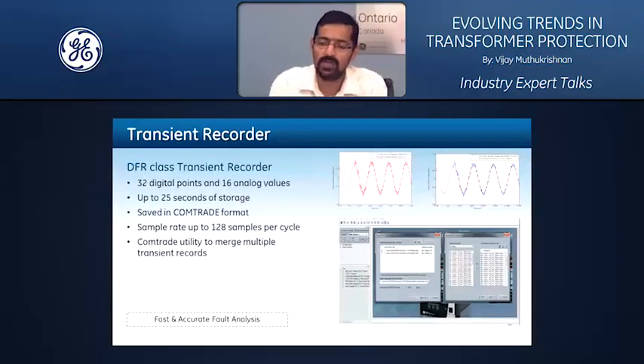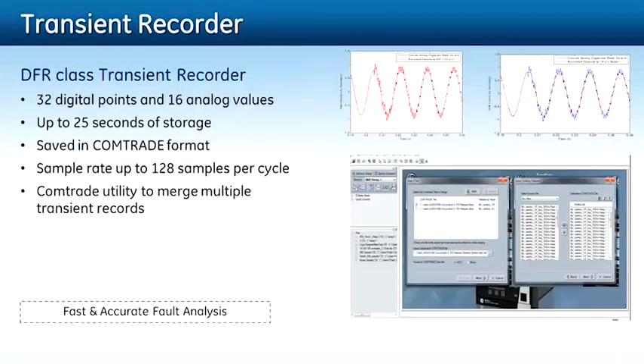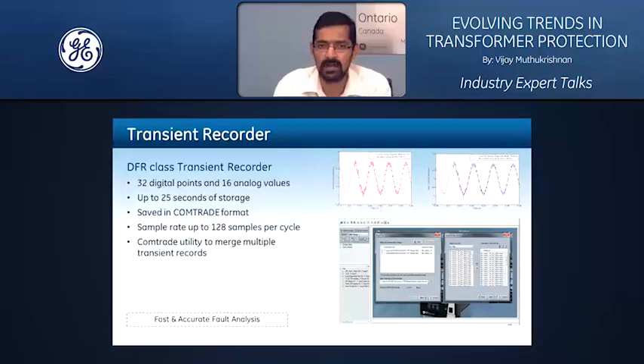Now, let's move on to some of the tools that you normally use for troubleshooting. When you actually have a fault, whether it is a through fault or an internal fault, what type of tools are available within the protection relay that you can use to make the analysis after the event simple, fast, and accurate? So the first one is the transient recorder, or oscillography. The transformer protection relay should be able to provide almost a DFR class transient recorder with sampling rates as high as 128 samples per cycle, with the ability to configure the sampling rate you want to pick, up to 25 seconds of storage depending on the sampling rate you choose, and a software tool that is very easy to use to visualize the COMTRADE files and make sense out of what type of fault has happened, where the fault is, and what actions you want to take.